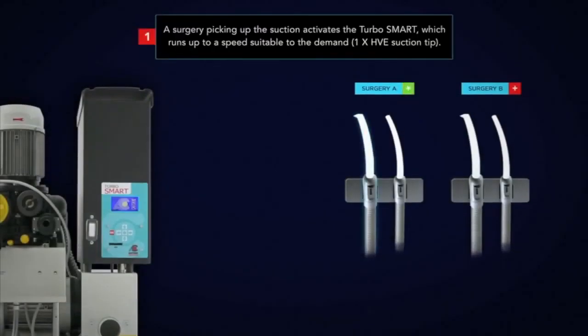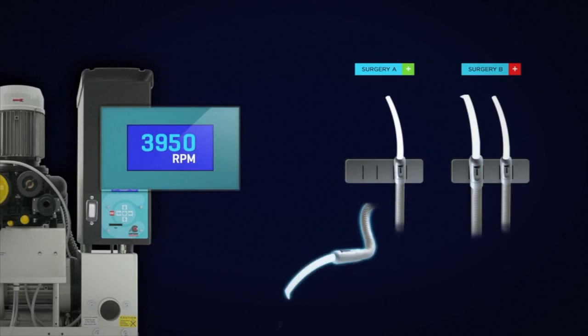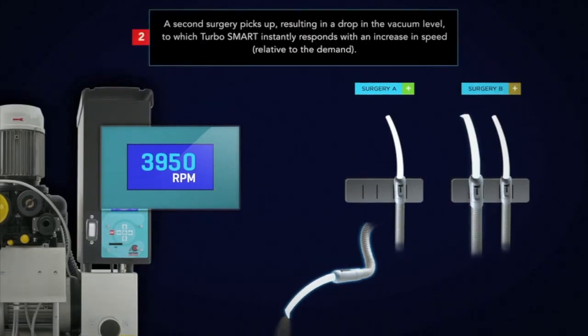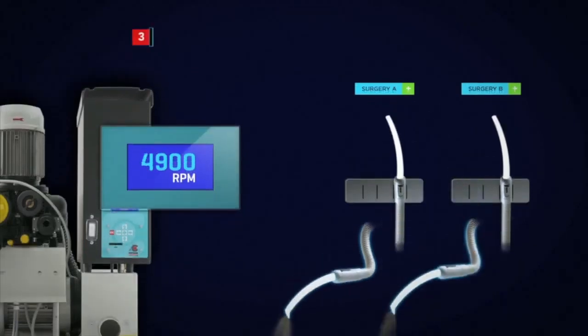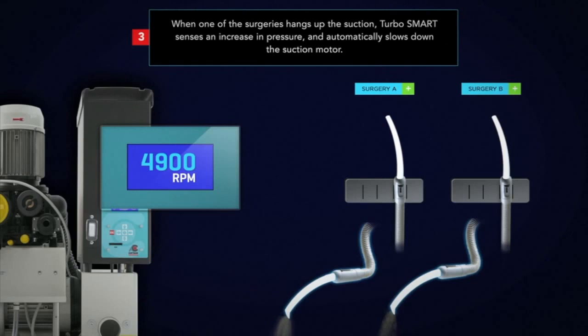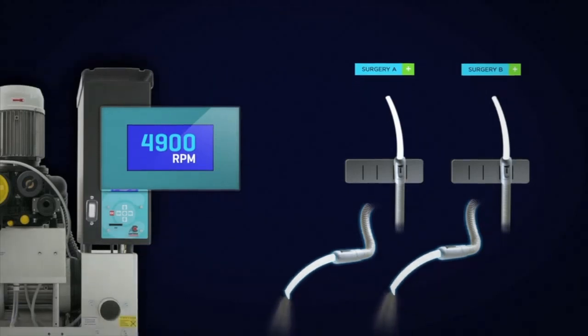Cattani Variable Speed Suction. A surgery picking up a tip and therefore calling for suction will activate the TurboSmart. TurboSmart will always try to achieve a negative vacuum of 210 millibar. Then when a second surgery picks up a tip, there is a slight drop in vacuum. TurboSmart will then instantly respond and will increase the speed to deal with the demand for both surgeries. When one of the surgeries replaces the tip, TurboSmart will sense an increase in pressure and automatically slow down the motor to simply deal with the one surgery that still requires suction.